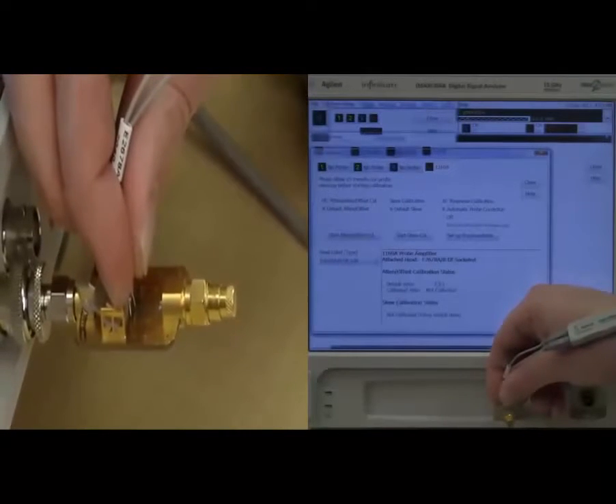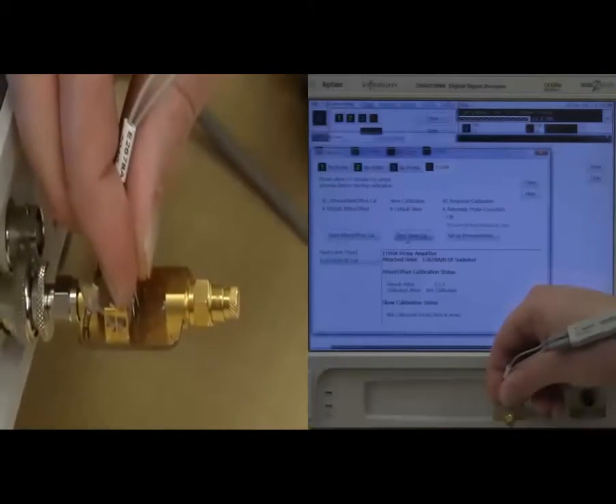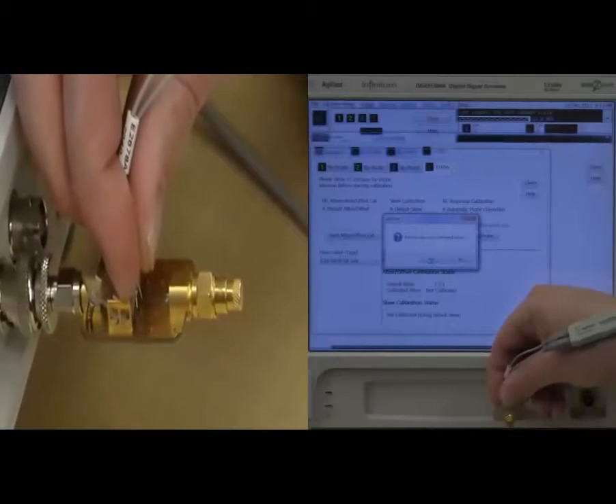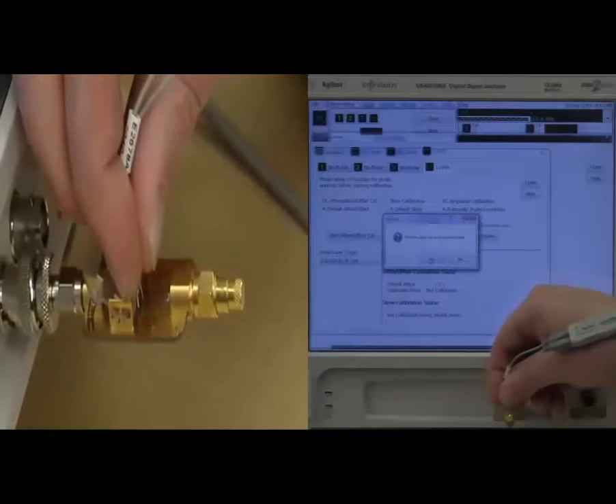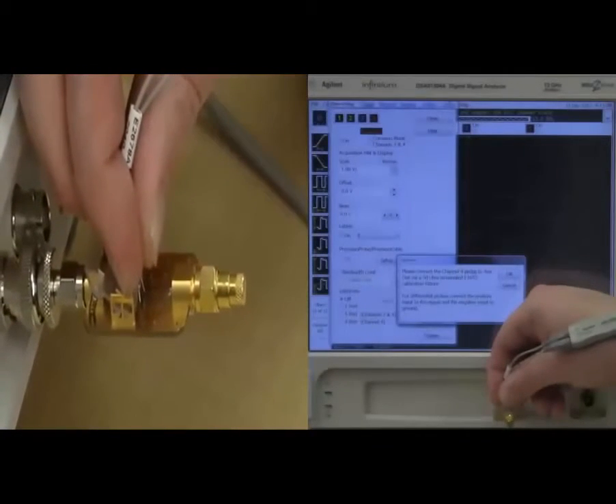Now, we can also do a skew-cal. This is really for channel 1 to channel 2 to channel 3 when using probes. I can simply hit start skew-cal. It's very important to have the 50-ohm load since it does source a fast edge into the calibration fixture. And without the load, we get a large reflection.